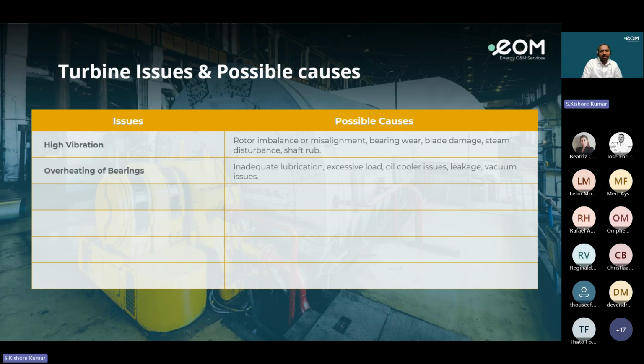Coming to the overheating of bearings because of inadequate lubrication, as I already said, if the lube oil ports are not cleaned or are clogged, proper lubrication is not there. So it will cause overheating of bearings, and also excessive load. Sometimes there are oil cooler issues, as sometimes we do not take a look at the oil coolers, and that causes issues. Sometimes the cooler is not working, or the three-way control valves which have to pass that hot oil to the oil coolers in order to cool are not opening properly. So the hot oil is fed directly to the bearings, which will overheat them and cause bearing damage, and also leakage and vacuum issues.